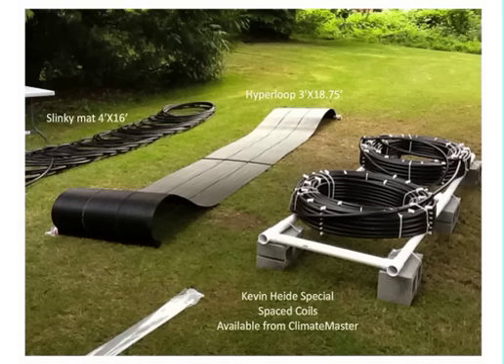Slinky mat is the one I preferred - I did a lot of these. One thing I'd do is take some long 2-inch pipe, typically drill a bunch of holes along its full length, put a cap on one end, and put it on top of each slinky mat. Then I'd put another slinky mat on top of that, cinch the two together with nylon zip ties, and stack them up vertically with those 2-inch separation pipes.